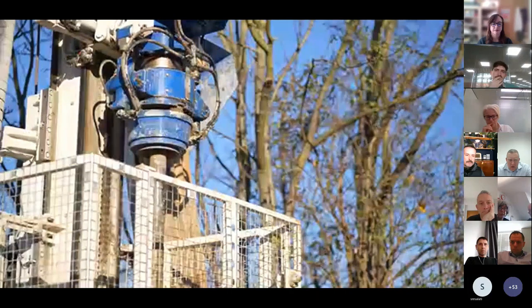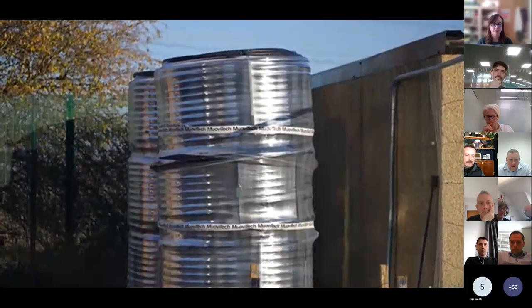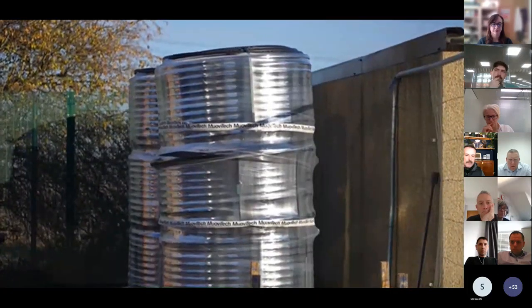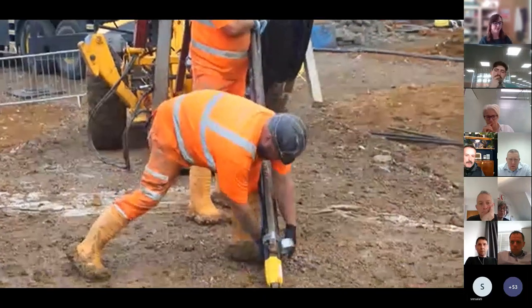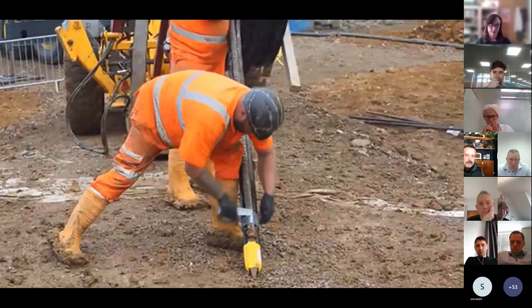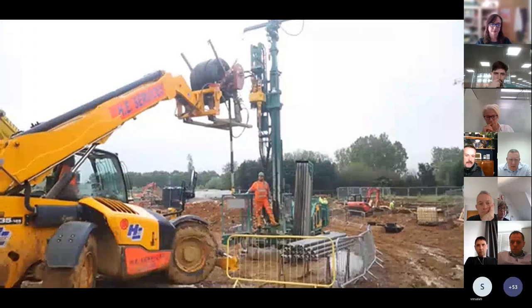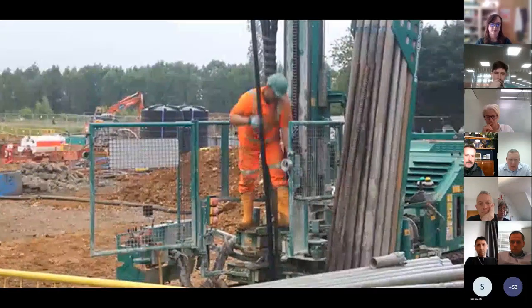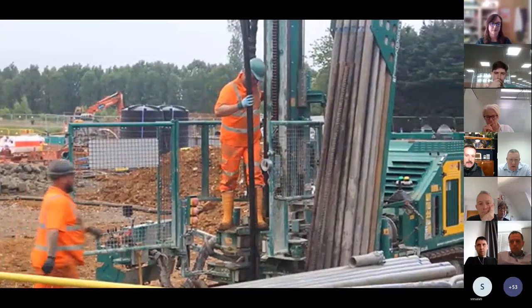Once the borehole's been drilled to depth, it's then time to insert the borehole probe. We've got a continuous length of 45 mil HDPE pipework with a fusion weld connection at the bottom. That probe is lowered into the hole, and it's meter marked, so we know that we've got the probe all the way to the bottom.